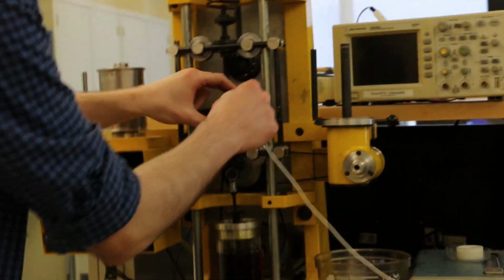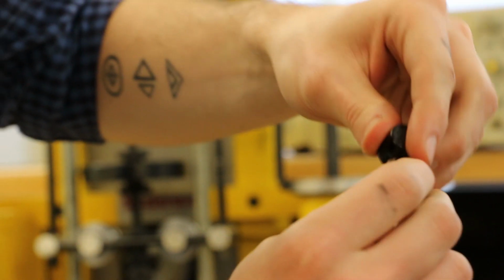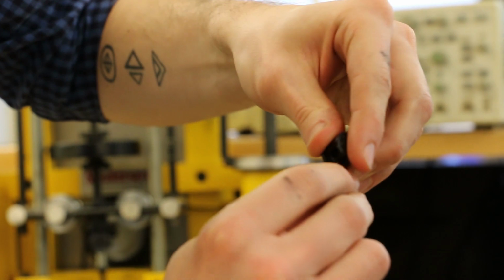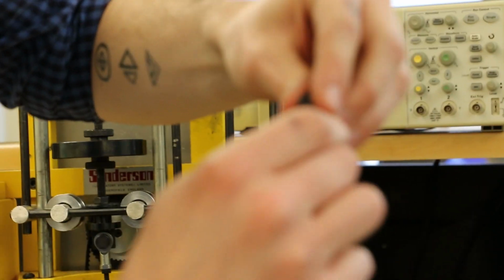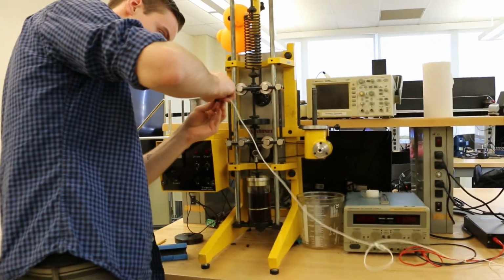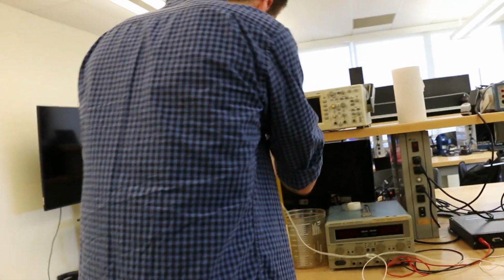We're gonna plug it into our signal conditioning box right over here, and make sure you stick it in the pinhole here. And make sure you tighten it all the way, otherwise you're going to get noisy data, which is never fun. Once you get this in here, all the way, stick that on the mass.